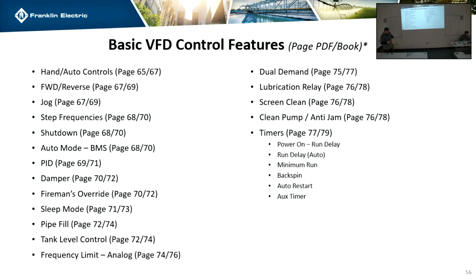For auto, same thing, keypad. Auto has up-down digital input, so you can program the digital inputs. If you have like a button, you just hold it and it'll slowly go up, hold the other one and it slowly goes down. You can set that up if you want. AVI just like hand, ACI like hand, AVI2 is like hand, comms, and then PID output. So if you're going to be using PID, even for HVAC, you go into auto speed ref and you tell it to look at PID, and then once you get into the PID, that's where you're going to set up what input you're actually looking at to get controlled.